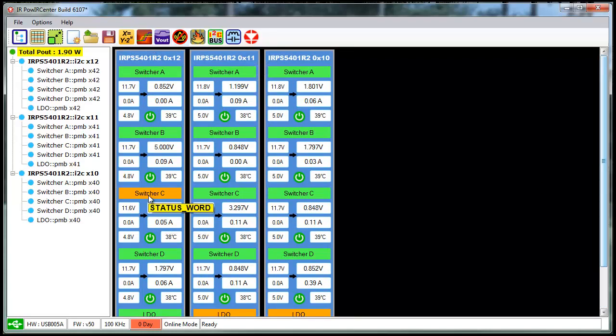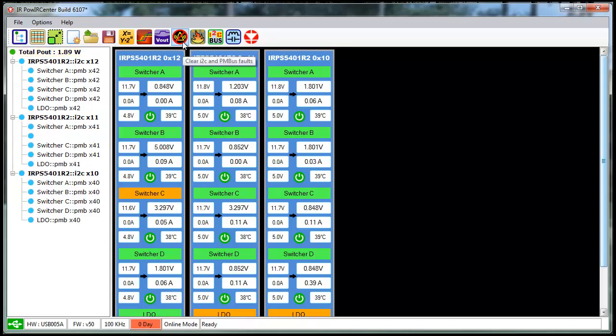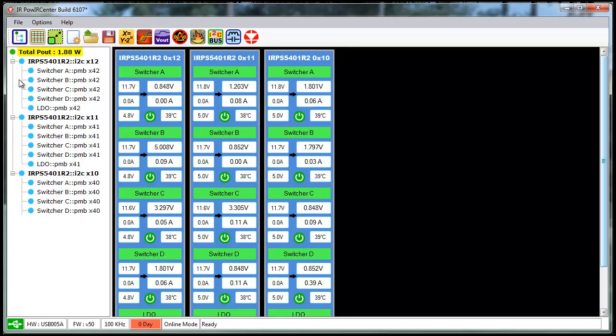Sometimes you'll hit some of these threshold warnings during power-up. So what I like to do is after power-up, issue a clear, then you can monitor for any actual operational faults.